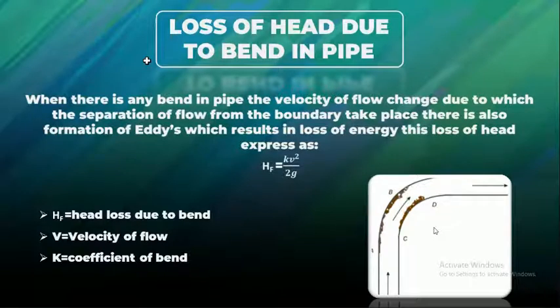This loss of head equals h_f is equal to k times v squared by 2g, where h_f is head loss due to bend, v is velocity of the flow, and k is coefficient of bend.